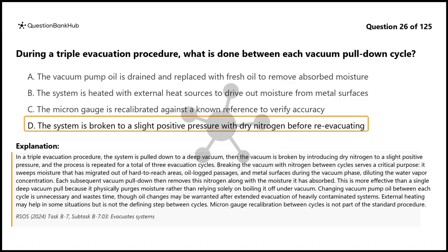This is more effective than a single deep vacuum pull because it physically purges moisture rather than relying solely on boiling it off under vacuum. Changing vacuum pump oil between each cycle is unnecessary and wastes time, though oil changes may be warranted after extended evacuation of heavily contaminated systems. External heating may help in some situations but is not the defining step between cycles. Micron gauge recalibration between cycles is not part of the standard procedure.